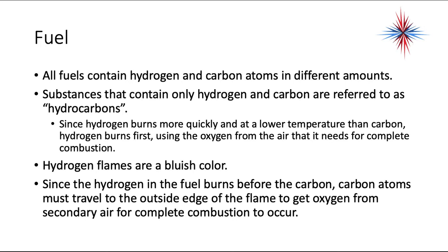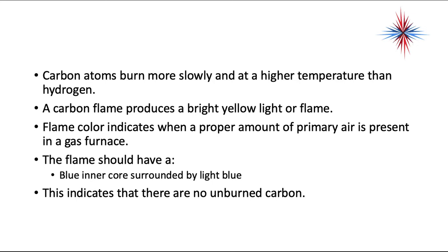All fuels contain hydrogen and carbon atoms in different amounts. Substances that contain only hydrogen and carbon are referred to as hydrocarbons. Since hydrogen burns more quickly at a lower temperature than carbon, hydrogen burns first using the oxygen needed for complete combustion. Hydrogen flames are a bluish color. Since hydrogen burns before carbon, carbon atoms must travel to the outermost edges of the flame to get oxygen from secondary air. Carbon atoms burn more slowly at a higher temperature and produce bright yellow light. Flame color indicates when proper amounts of primary air are present — a perfect flame should have a blue inner core surrounded by lighter blue, indicating no unburned carbon atoms.